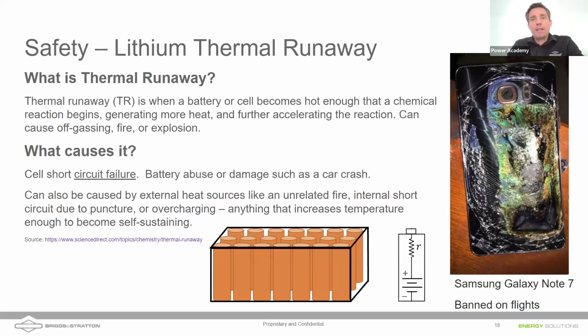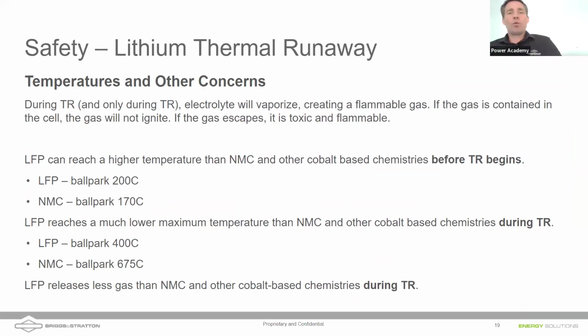Our 9540A tests that we publish show that. What does happen in thermal runaway in NMC cells is you reach higher temperatures with a much more rapid release of energy. The overall temperature of an NMC cell in thermal runaway is typically higher, reaching temperatures like 675 Celsius, which is quite hot. Thermal runaway can happen at lower thresholds, like 170 C for an NMC battery, versus an LFP battery, where you have to get it much hotter to trigger that off-gassing event.